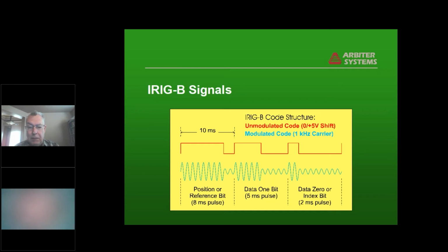Most applications in the power industry use the unmodulated or level shift code, and that's basically just a digital binary signal, 0 and 5 volts. Some applications, RTUs, in some cases, still use a modulated code. That has the advantage it can be transmitted over an AC line, like a telephone line. It's basically a 1 kilohertz signal that's amplitude modulated in accordance with the same code that's put on the unmodulated signal.